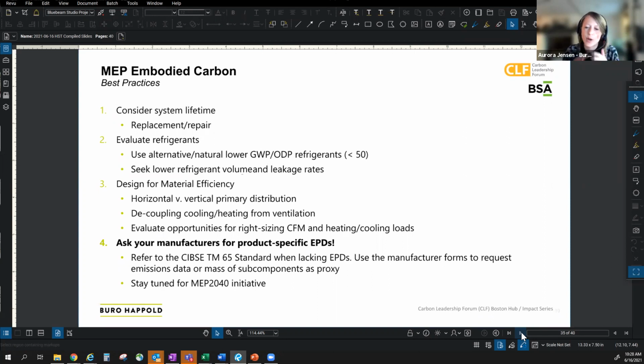Evaluation of refrigerants is partially an embodied carbon problem, but it also interacts with the operational side in huge ways. At Buro Happold we've been putting a lot of emphasis on evaluating alternative and natural refrigerants, often looking for GWP of less than 50, looking at refrigerant volumes, as well as examining leakage rates. Refrigerants tend to leak during installation of the equipment, during the life of the equipment, and then also at end of life when that system maybe gets dumped in a landfill. So thinking through what that might mean in terms of deconstruction or reuse of these systems could be huge in changing that picture.